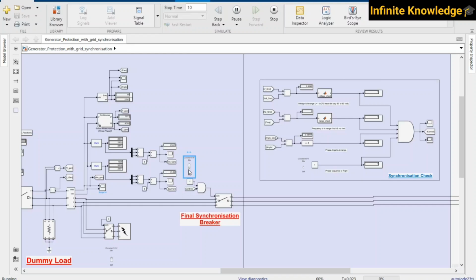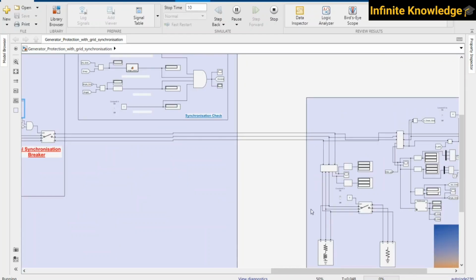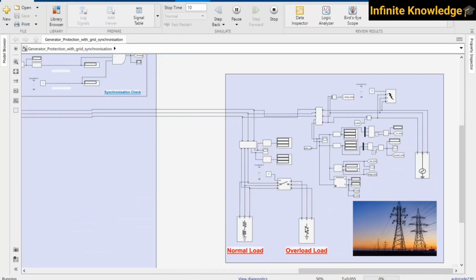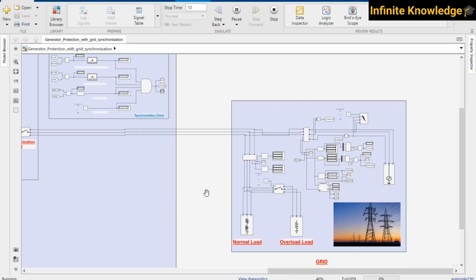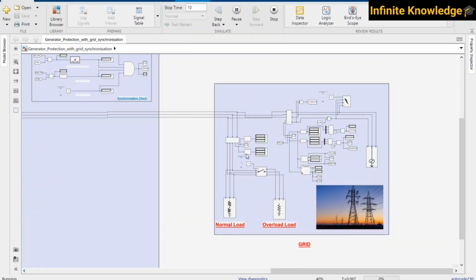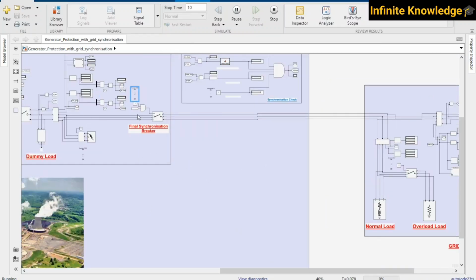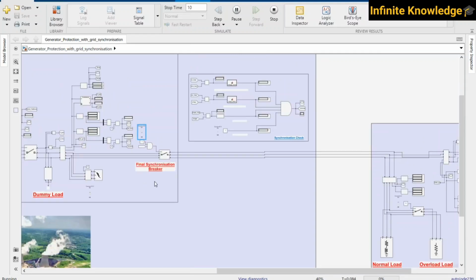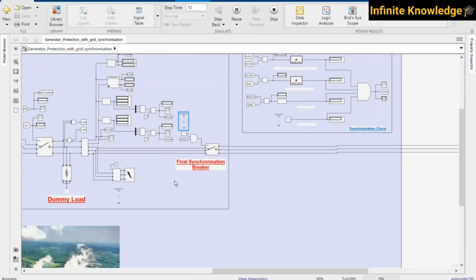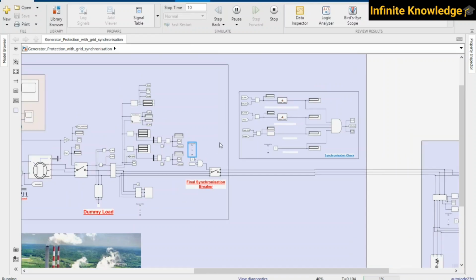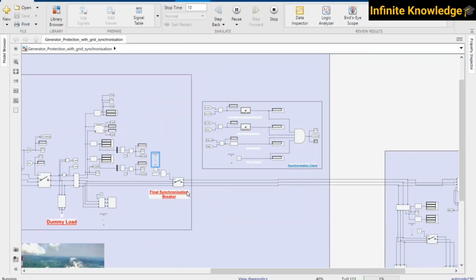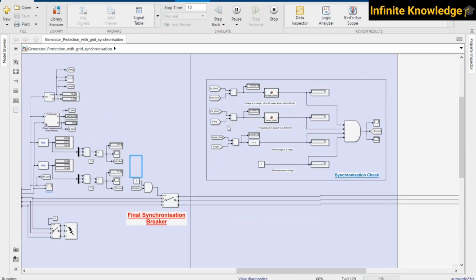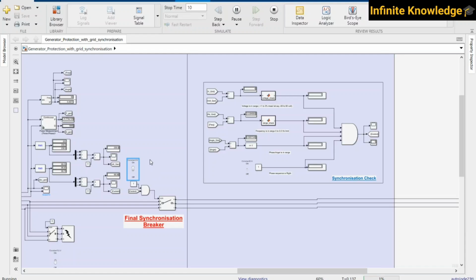As I press the switch, you can see that our system, our generator, is synchronized with the grid. This entire grid, you can say it is a national grid, and this is your power station, and you are connected. Yes, obviously voltage levels do not match, right, but this is how the system works. You can just use a transformer to step up and step down, you can do it over here, but our main concern is to check this voltage, frequency and current and synchronize satisfactorily.